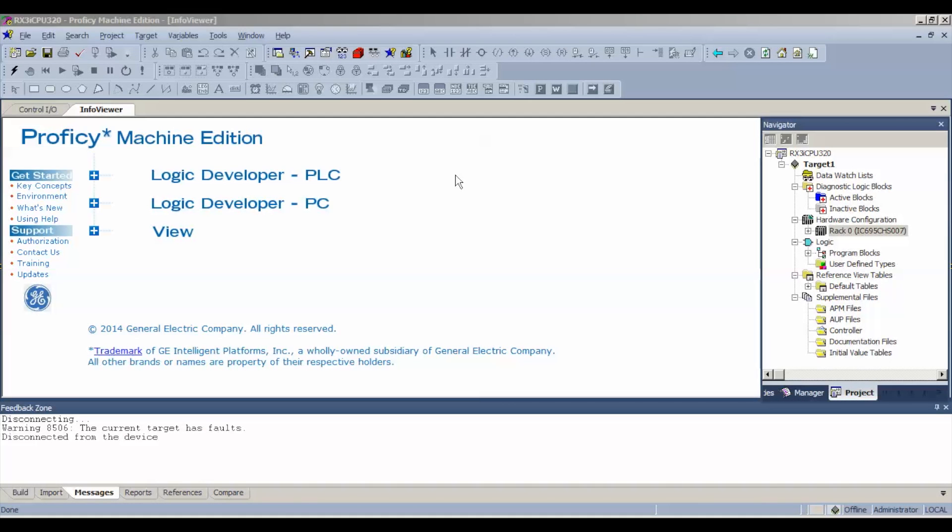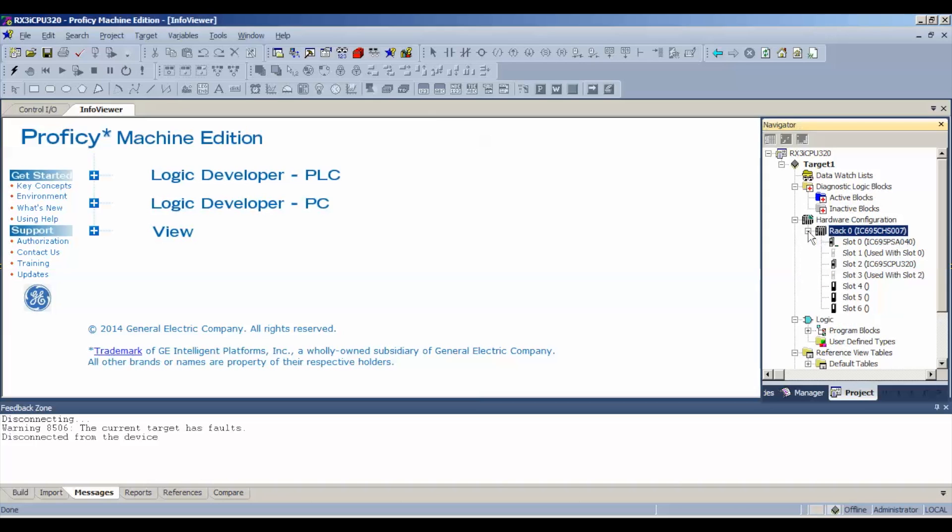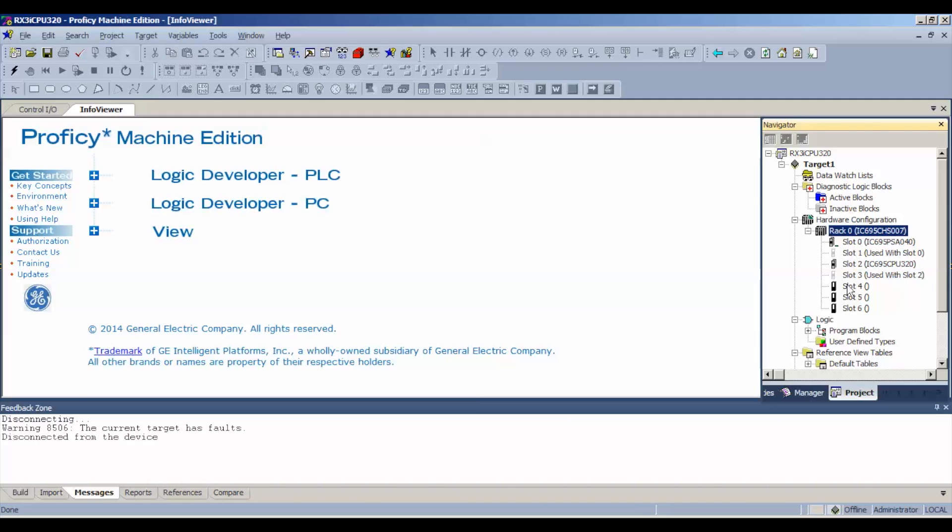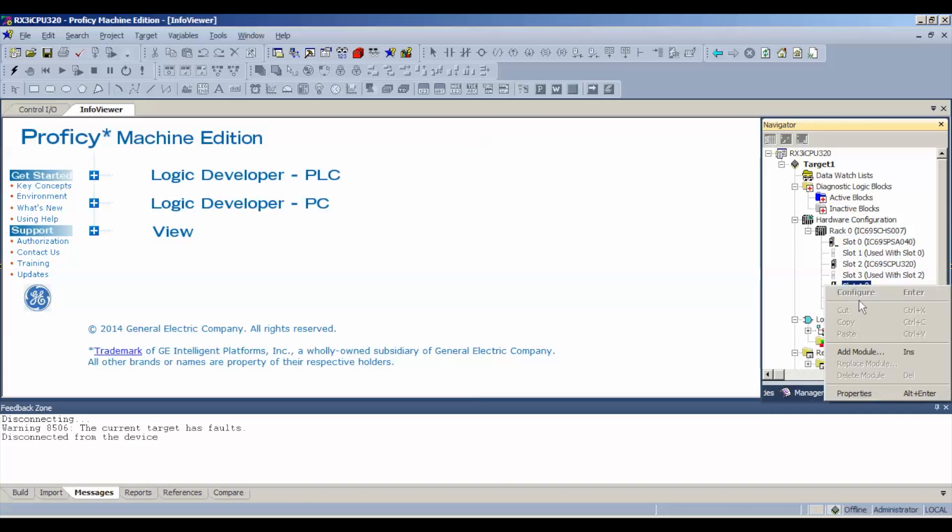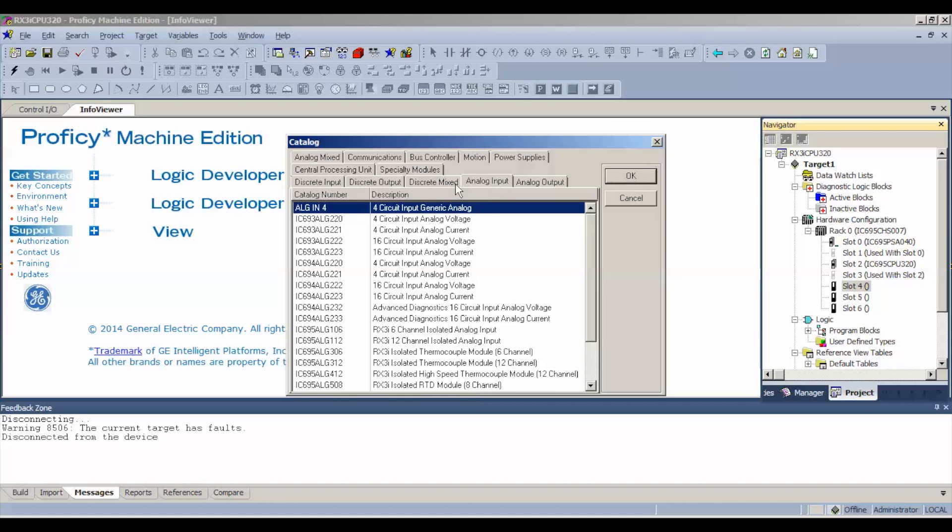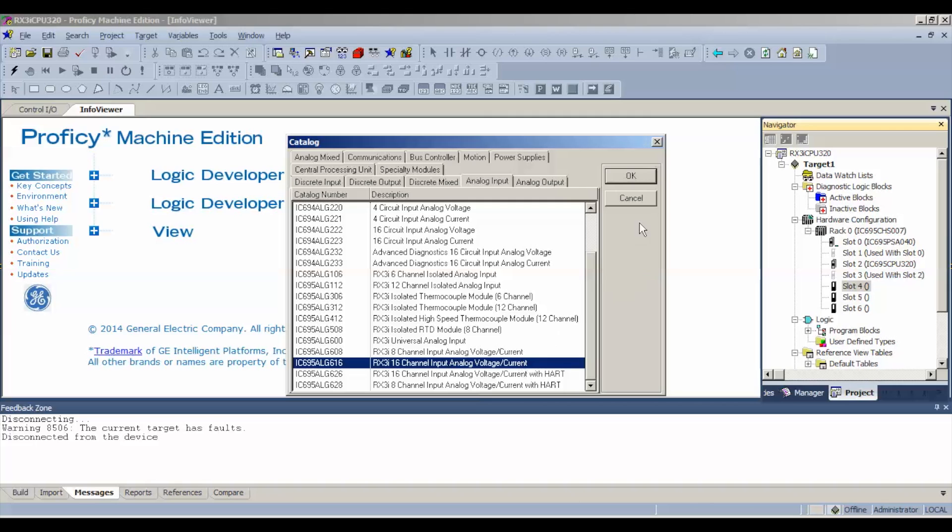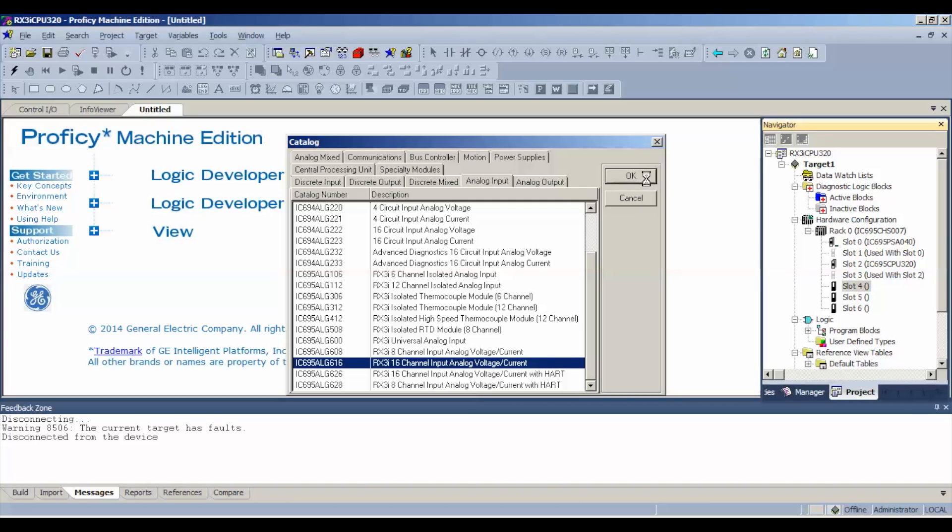The next thing we're going to do is get into the software end of it. I'm using Proficy Machine Edition and I have an open blank file here. The first thing I want to do is go to Navigator, expand on my rack. I'm using a CHS007. You can use a CHS012 or 016 to follow this test. My power supply is using slots 0 and 1, it uses two slots. The CPU, I'm using an IC695 CPU320, is using slots 2 and 3. That's important to note because the next available slot that you're going to be able to use is slot number 4.